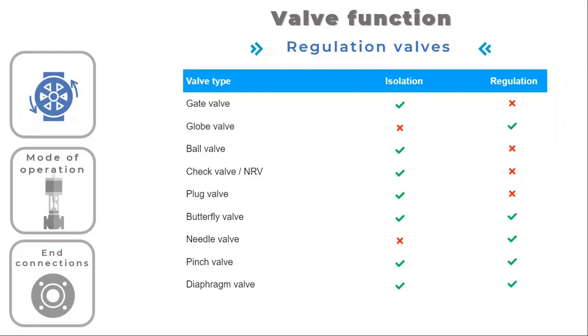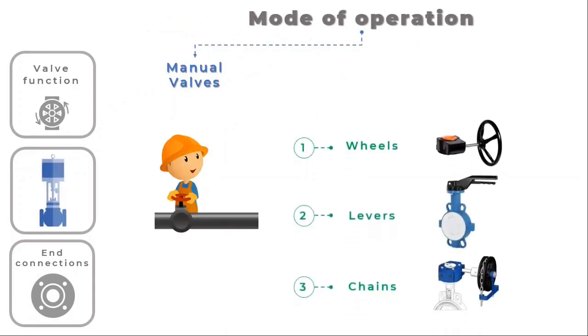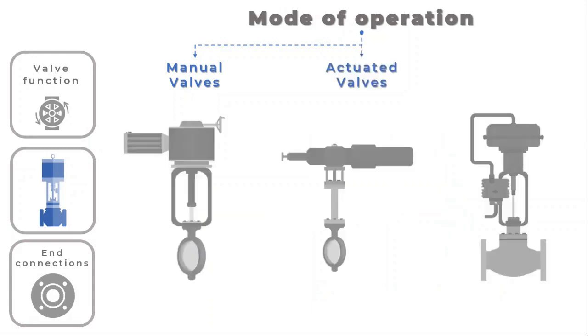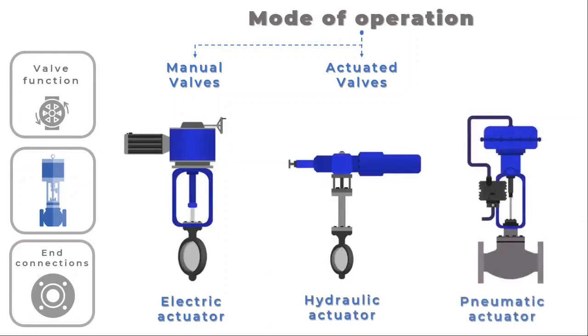Based on how they are operated, valves can also be categorized as manual, actuated, or automatic. To manually operate a manual valve, wheels, levers, or chains are frequently used. These valves can be geared mechanically to alter moving direction as well as to speed up or enhance torque. Valves are frequently coupled to electric motors, hydraulic systems, or pneumatic systems in high-precision or large-scale applications to enable remote operation and automation of valve performance.